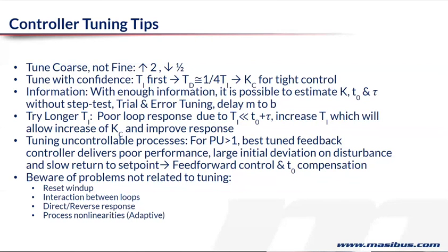And process nonlinearities, we just talked about process nonlinearities, the steam heater equation. If you are increasing the flow through the steam heater and you lose control, you should know that this is a nonlinear process, and now is the time to retune because the process flow has increased, or you adopt a feed forward algorithm so that it will automatically compensate for that increase in flow.